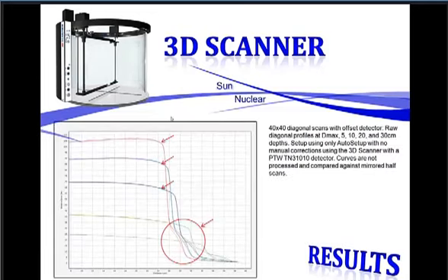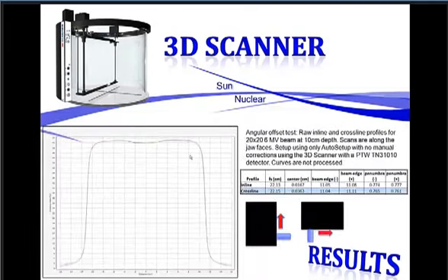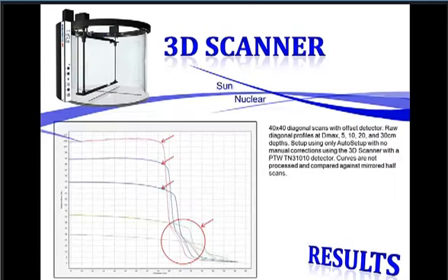When we commissioned, we also looked at the functionality of the tank that they claim that you can scan a full diagonal profile. A lot of us scan half profiles in the IBAs for years and years and mirrored them because they're symmetric. So we wanted to test that functionality during the number of our commissionings. This slide is very reminiscent of what we see on our commissionings, that there is some asymmetry to those diagonal scans. One of the things that you can kind of throw out is when you are doing those diagonal scans that if you have checked the jaw face, if you're skewed, these asymmetries can happen. But if you get nice scans like the previous slide where you have these nice flat profiles at the 50% line, you know your jaws aren't skewed, so you know you're scanning across a true diagonal.